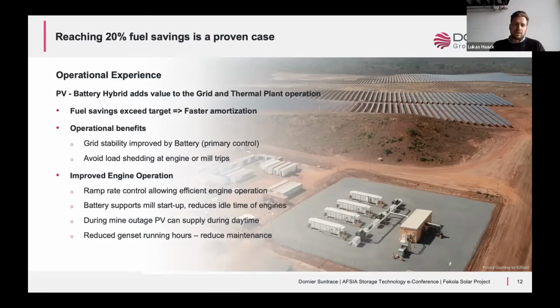Another point on actual plant operation: when you start up a mill, you need to supply a certain amount of inrush current for the mill drive, the mill motor. Usually you need engines ready in a low load situation, waiting for the mill to start, to supply the inrush current needed. Here the battery system can support this process and allow you to run with fewer engines during mill startup, keeping them in more favorable load conditions. So this is another benefit, though I didn't have time to put a respective graph.